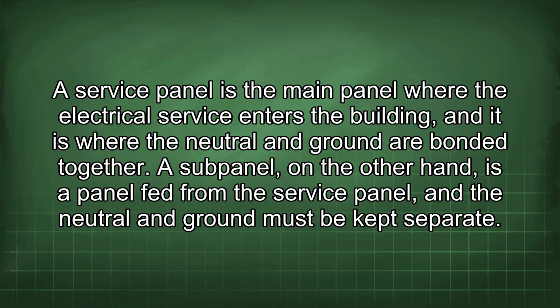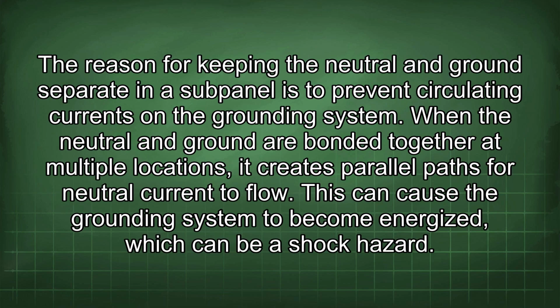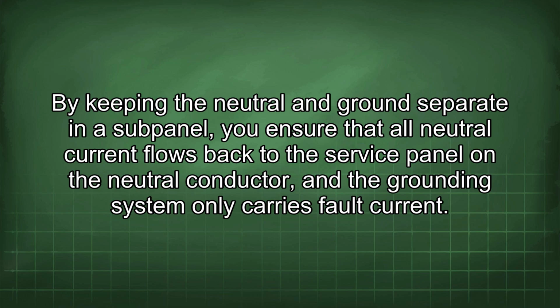A subpanel, on the other hand, is a panel fed from the service panel, and the neutral and ground must be kept separate. The reason for keeping the neutral and ground separate in a subpanel is to prevent circulating currents on the grounding system. When the neutral and ground are bonded together at multiple locations, it creates parallel paths for neutral current to flow. This can cause the grounding system to become energized, which can be a shock hazard. By keeping the neutral and ground separate in a subpanel, you ensure that all neutral current flows back to the service panel on the neutral conductor, and the grounding system only carries fault current.